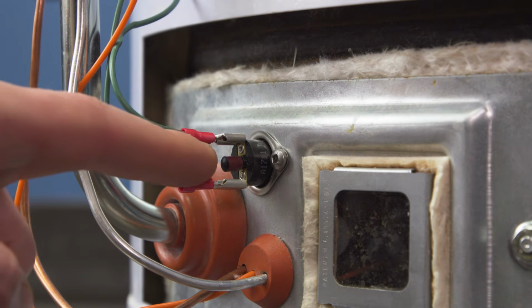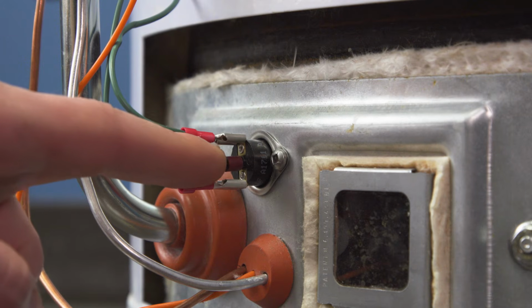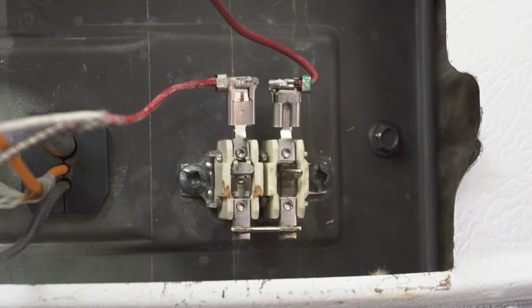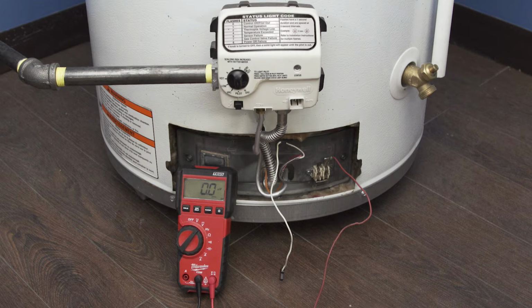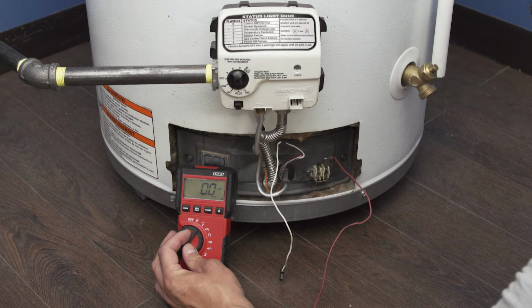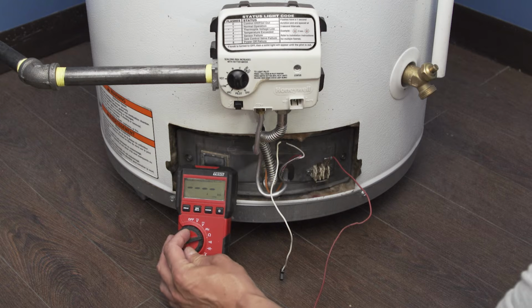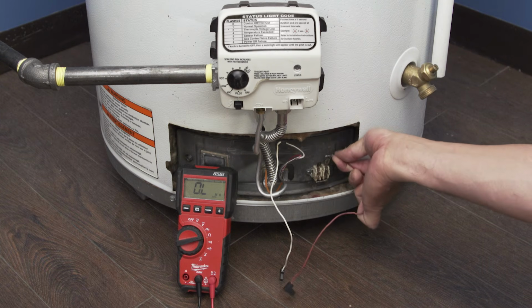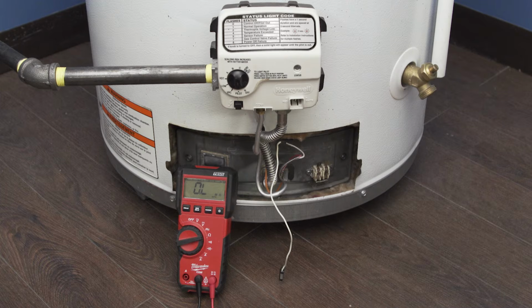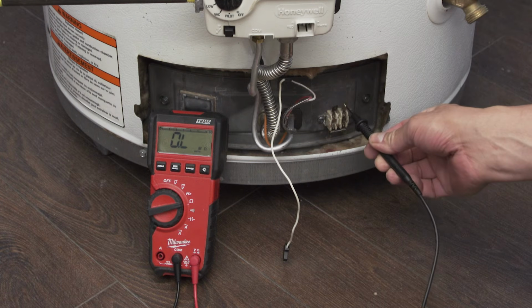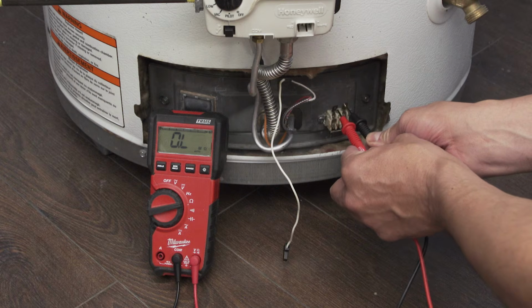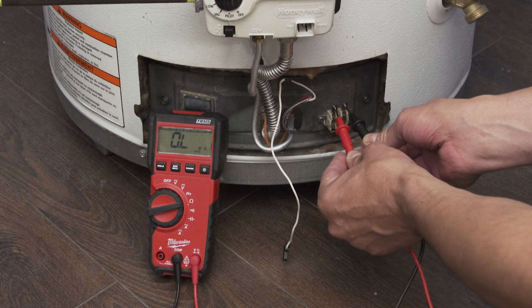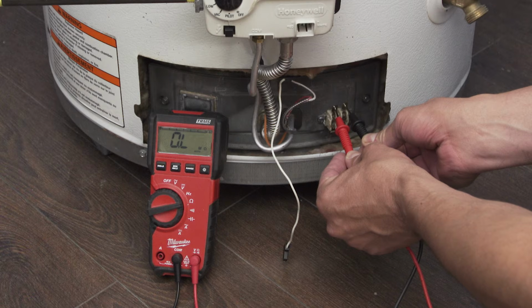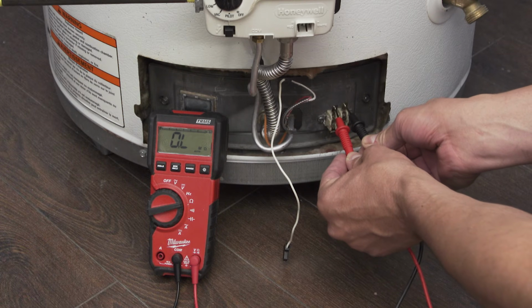Not all thermal switches have a reset button. Some will reset automatically, and some water heaters will use a one-time fuse. Regardless, you can test the switch for continuity to see if a continuous electrical signal can pass through it. First, set the multimeter to the ohm setting. Disconnect the wires to the switch. Place the probes on the terminals. If the multimeter reads OL or open loop, then there's no continuity and the switch should be replaced.